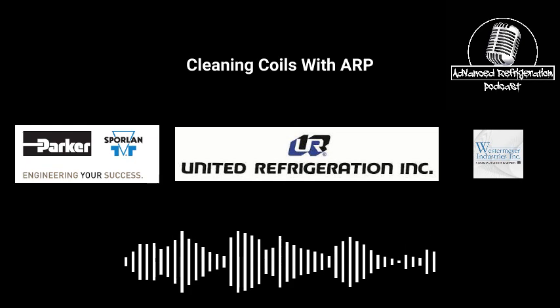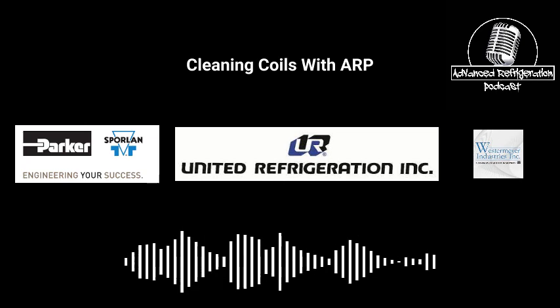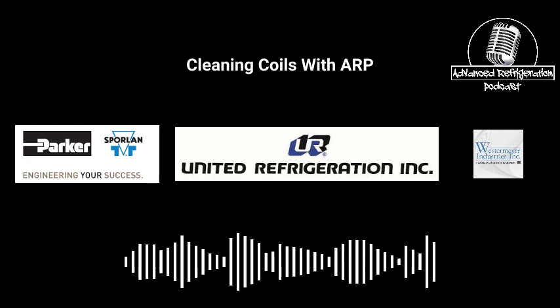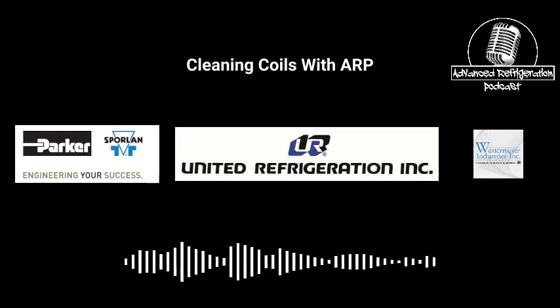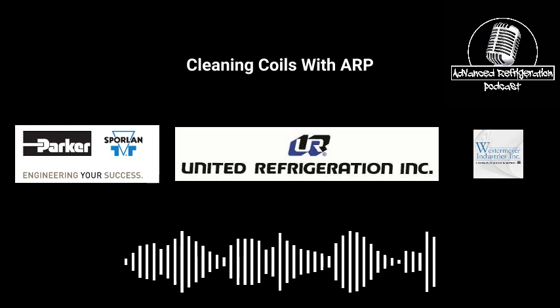You are there to make sure they wash the condenser properly. The only person getting screwed by them not washing that condenser properly is you and your company, because you're going to be the ones running the calls when it's 95 degrees outside and that condenser wasn't washed properly, but it looks clean. And then there's a sprinkler running on it, and now you've destroyed equipment. A sprinkler should be the last option. If the equipment's trash, it's trash. But a sprinkler should be the last option.